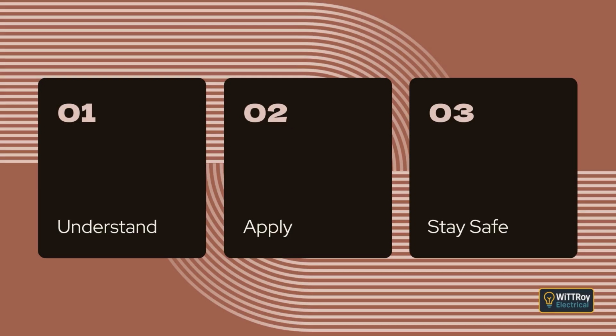Section 1.5 Fundamental Principles. Clause 1.5.2 Control and Isolation. Now we look at control and isolation. Every installation must allow the circuits to be controlled and isolated safely. Control is the everyday switching, turning things on or off in normal use. Isolation is more serious. Isolation means disconnecting a circuit or a piece of equipment from all live parts, so that someone can work on it safely.